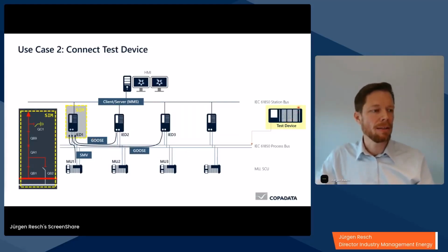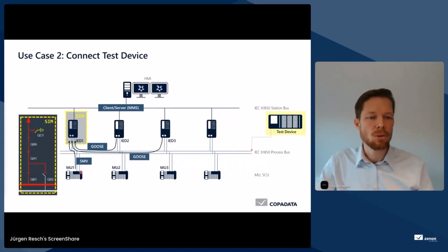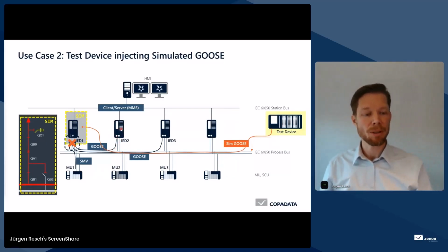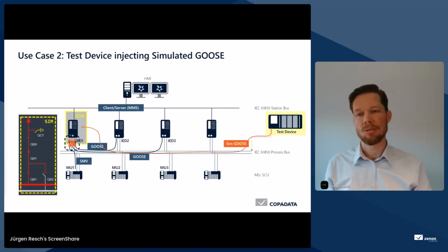And now the test device comes into the game, and we connect this device to our network. And as soon as the test device starts to inject GOOSE messages, for instance, the similarly configured messages coming from the IED2, then the device starts to only accept the simulated GOOSE messages, and it will ignore or block the other messages coming over the process bus, because now it is only subscribed to the simulated GOOSE messages.